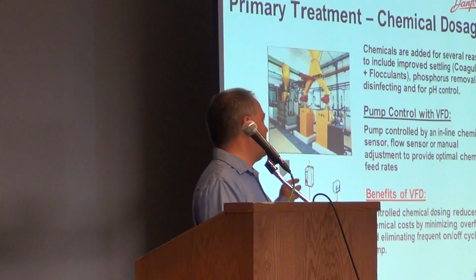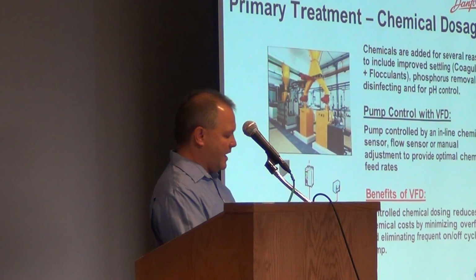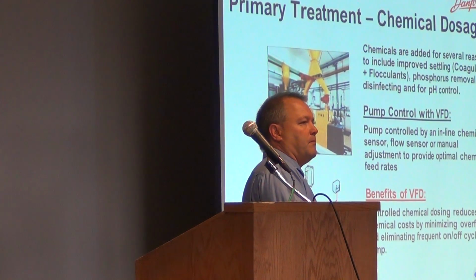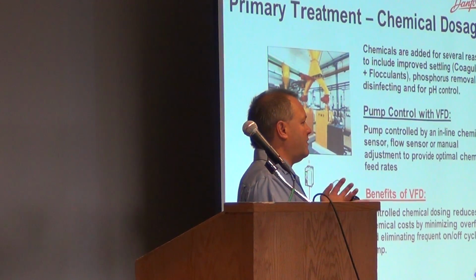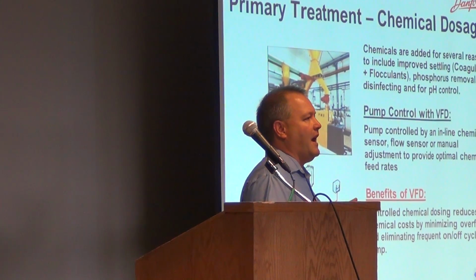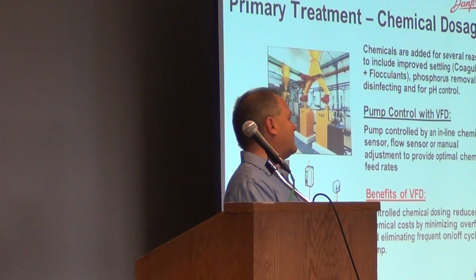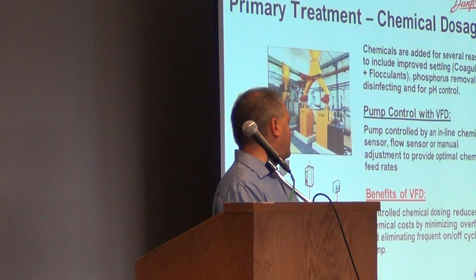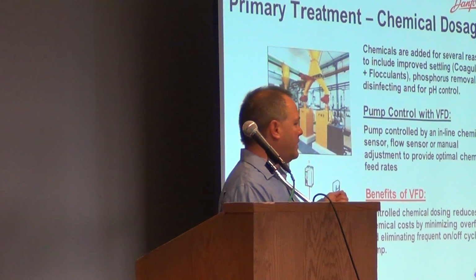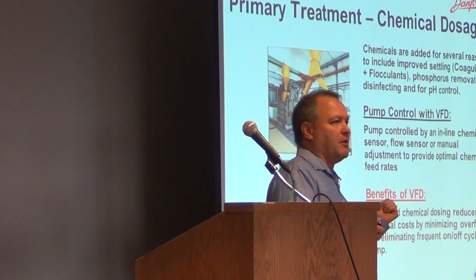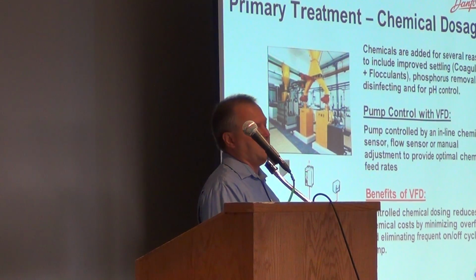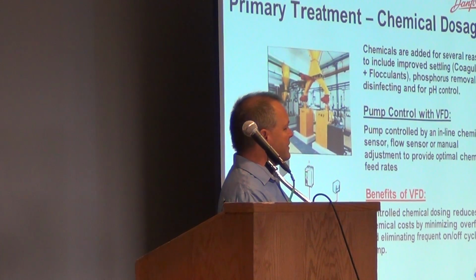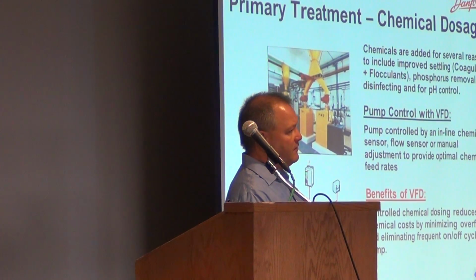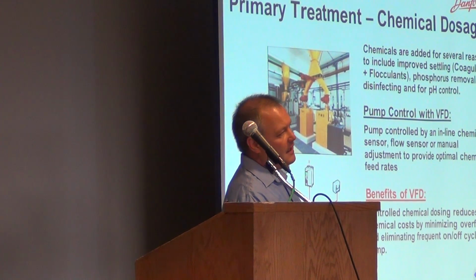One of the other benefits to a drive is we can help control the chemicals going into the system. The drive is controlling the flow, but it also has an analog output that can tell a chemical pump, all right, I'm running at 45 hertz or 3/4 speed, I don't need a full dose of your chemicals. You can give a variable speed to the chemical pumps to be able to tell it how much chemical it needs at the speed that it's running at. This is all done either through the SCADA system or drives. Our drives have enough intelligence to be able to help you out with that also.